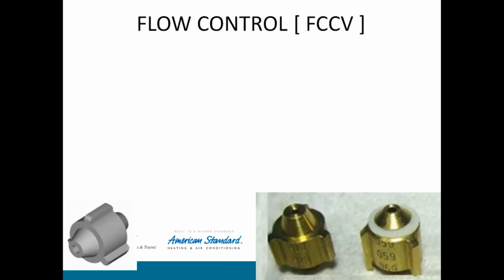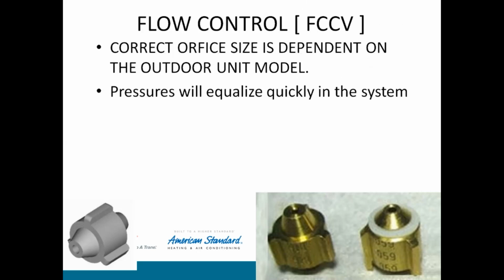All right, so there's a couple different ways that we meter, and I'm throwing these in here for a reason. If you're using a flow piston and you shut the system down, the pressures are going to equalize pretty quickly. Okay, so if it's an FCCV, a flow piston cap tube, you run it in the system, you shut it off, the high side and the low side are going to equalize pretty quickly.